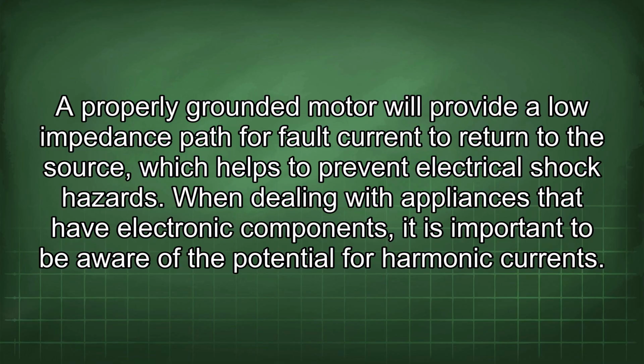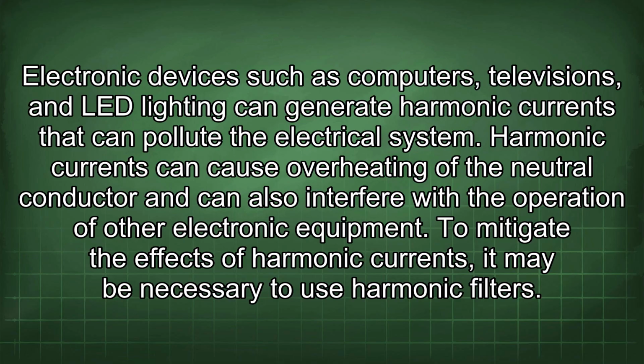When dealing with appliances that have electronic components, it is important to be aware of the potential for harmonic currents. Electronic devices such as computers, televisions, and LED lighting can generate harmonic currents that can pollute the electrical system. Harmonic currents can cause overheating of the neutral conductor and can also interfere with the operation of other electronic equipment. To mitigate the effects of harmonic currents, it may be necessary to use harmonic filters.